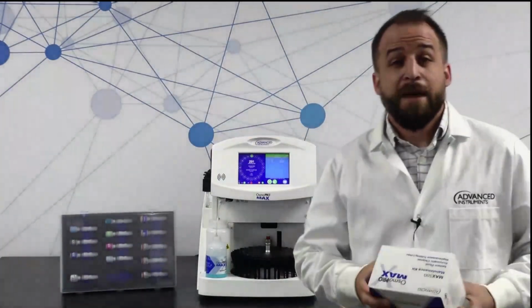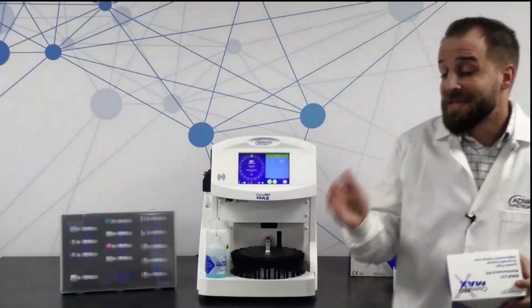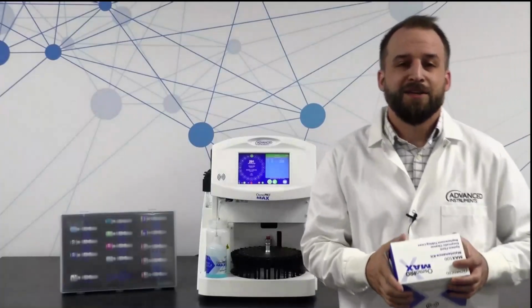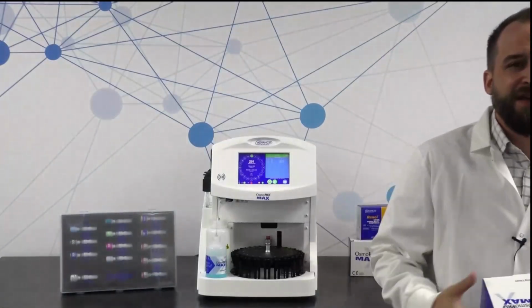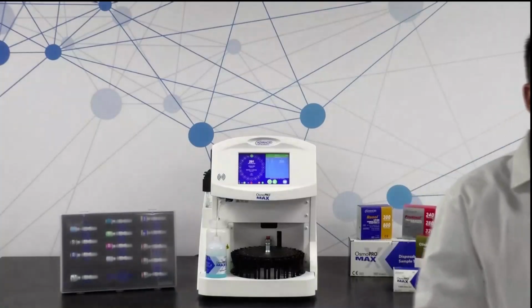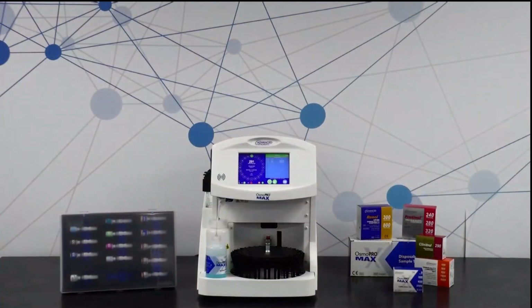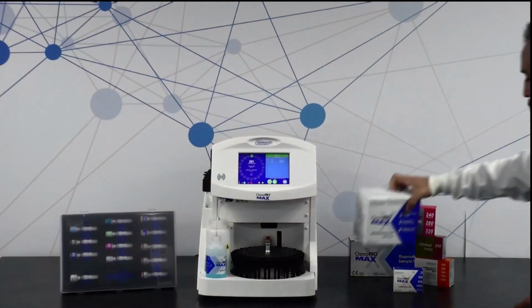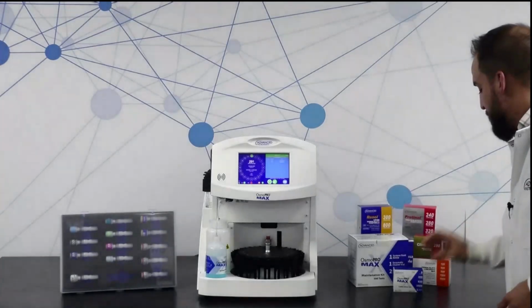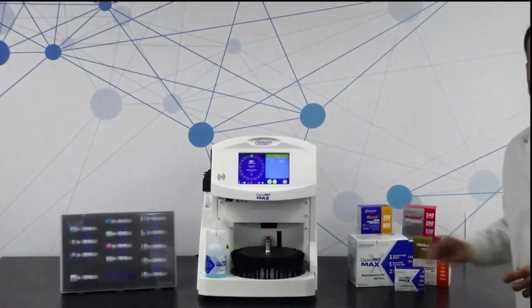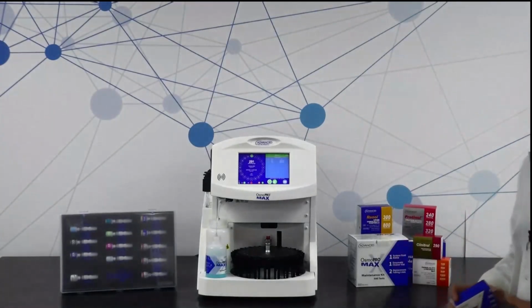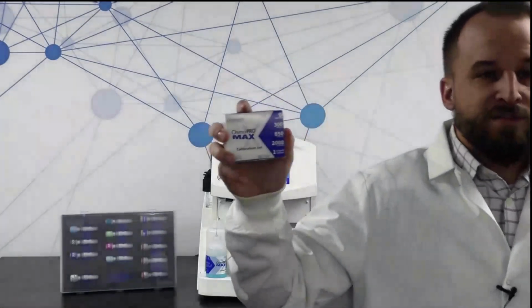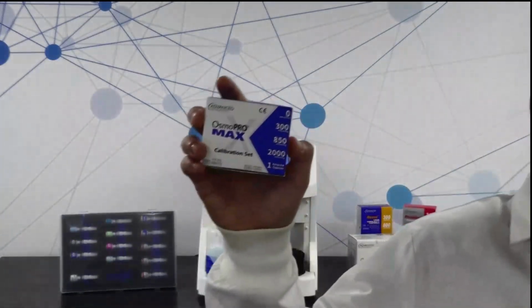The enzymatic cleaner is a pepsin-based enzymatic cleaner that's going to clean out that fluidic path, make sure that our flow-through system is staying clean, and ensure that we completely mitigate any risk of carryover, because we know we can't have that in our chemistry analyzer. Another thing that's great about this OsmoPRO MAX is this calibration kit.